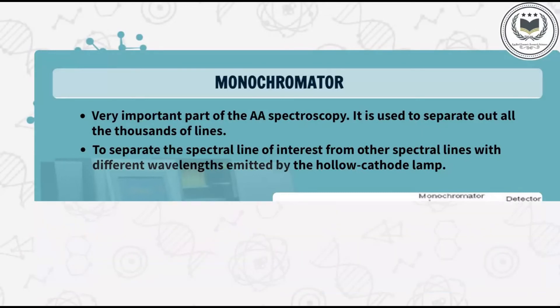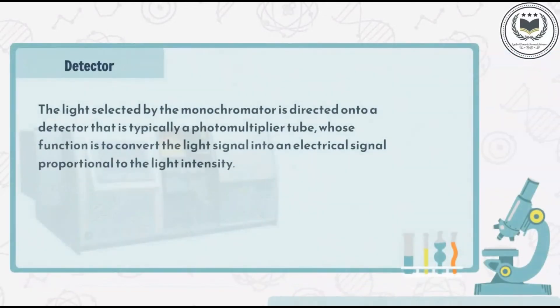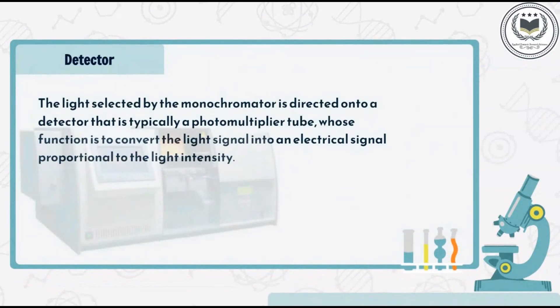The light selected by the monochromator is directed onto a detector, typically a photomultiplier tube, whose function is to convert the light signal into an electrical signal proportional to the light intensity. The most used detector in atomic absorption spectrophotometry is the photomultiplier tube, or PMT. No other device offers the same sensitivity over the wavelength range required for atomic absorption analysis.